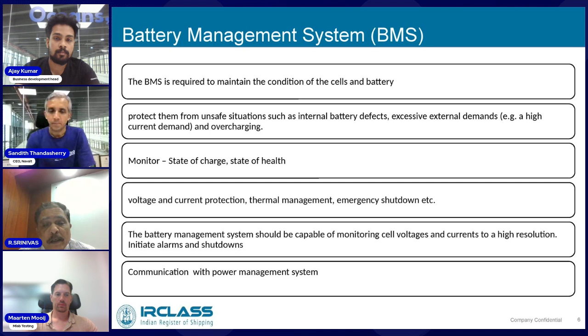So when to switch on the batteries, when to switch off, how the load sharing has to be done - these are handled by the main power management or energy management system in the main switchboard. The battery BMS has to communicate with the MSB for these issues.